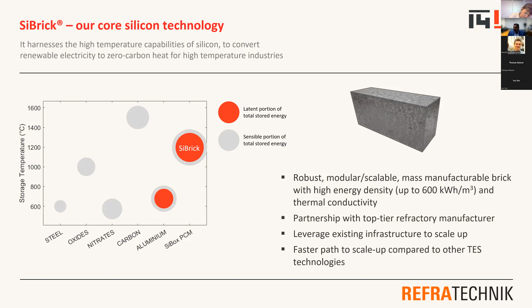The red portion in the middle is the latent portion of the total stored energy. Latent energy means that when the phase transition happens, it requires a certain amount of energy, and you can use that phase transition to store energy and recover it when required. About 55 to 60% of our total stored energy is in that latent phase, so we can cycle between a smaller delta T and still store a very large amount of energy. For reference, the bricks can store up to 600 kilowatt hours per meter cubed, and this is not from ambient - it's usable energy at a 900 degree Celsius output.